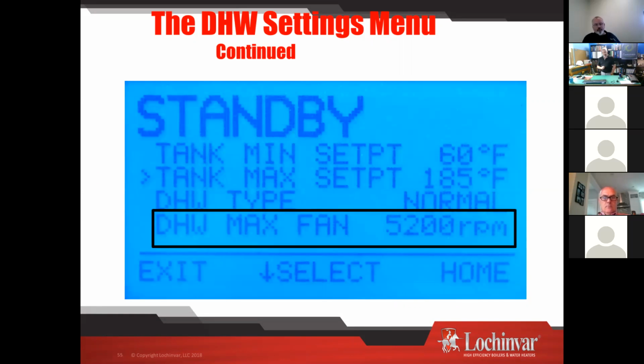Domestic hot water max fan. Now this is a pretty cool feature. We generally find a lot of times a boiler is oversized. Sometimes for the domestic hot water, we are beginning to see more where the domestic hot water is actually larger than the heating load. But if you have the case, and this might be more of a light commercial type of application, you put a 500,000 BTU boiler in and a 40-gallon indirect, obviously way too much boiler.